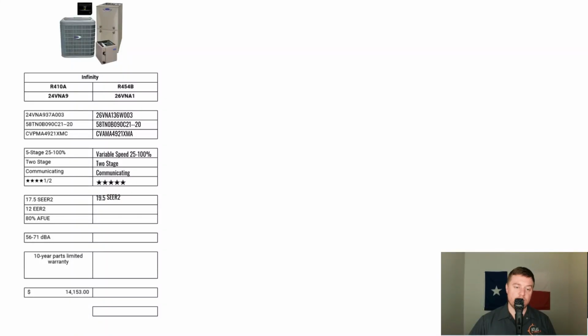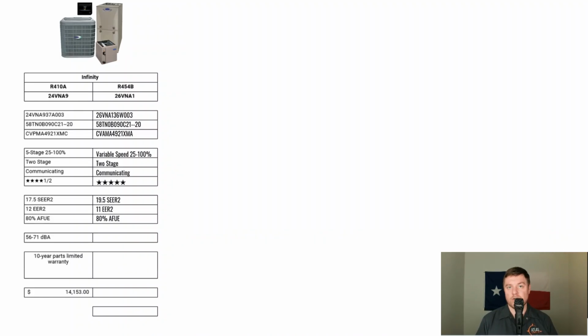Now if we take a look at the efficiency of these two systems, we can see that the 5-stage Infinity is able to deliver 17.5 SEER2, and the new variable speed system is able to deliver 19.5 SEER2, so a decent increase in efficiency. And the 5-stage is running a 12 EER2, and the new fully variable drops to 11 EER2. And keep in mind that the amount that you're going to be paying to the utility companies is going to be based on SEER and not EER. However, a certain EER is required to get rebates from the utility company when upgrading to a more efficient system. And for the gas efficiency, we are running identical furnaces, so there's no changes there.